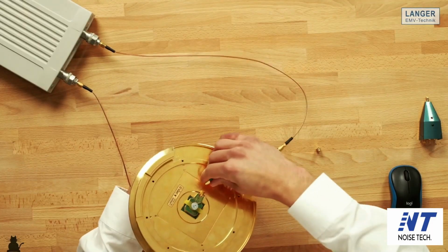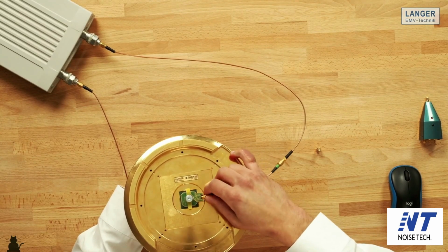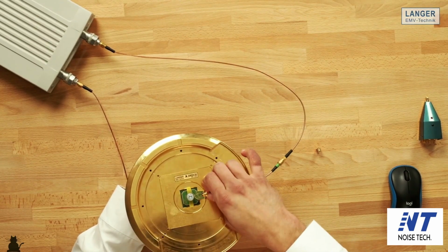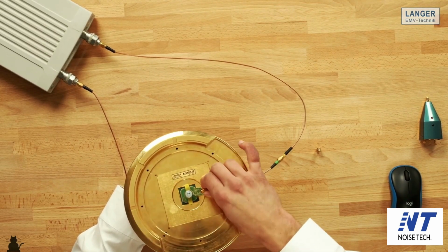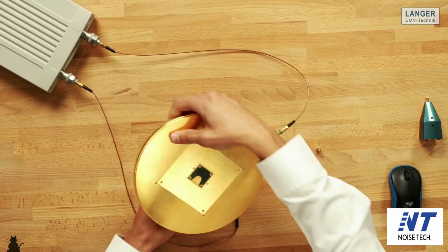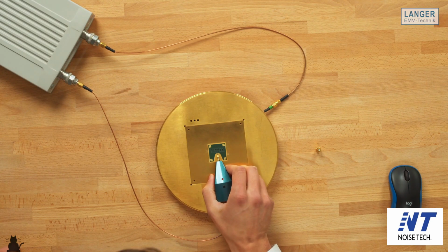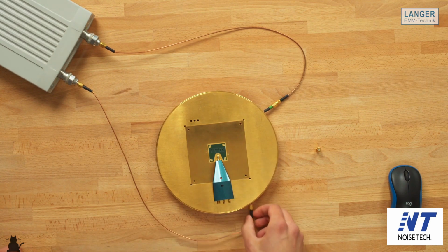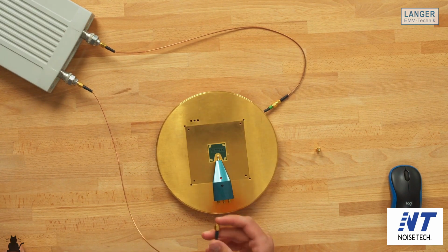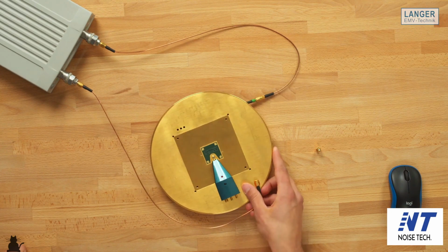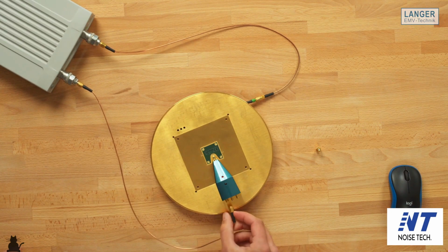To start measurements, we will start, of course, with the transmission curve of the P500. And this means we need to connect SMA to the calibration standard on the bottom. This is a SMA connector. So when it's tight enough, we will turn it around again. And now we have the probe, and we place it on the ground plane, like this. And for finishing the setup, we will now connect port 1 of the network analyzer to the SMA input of the probe.